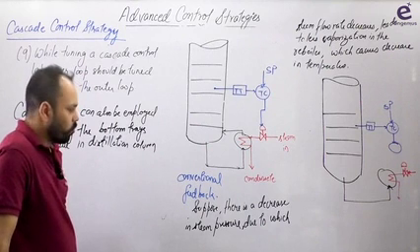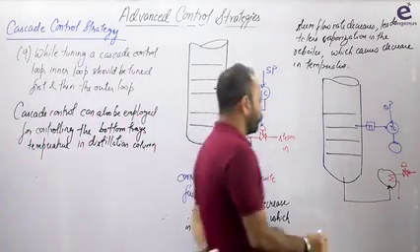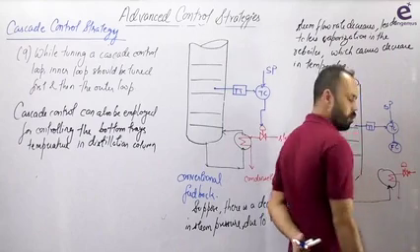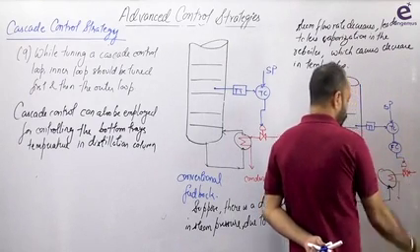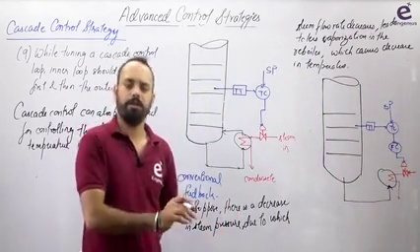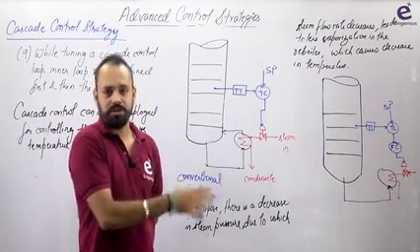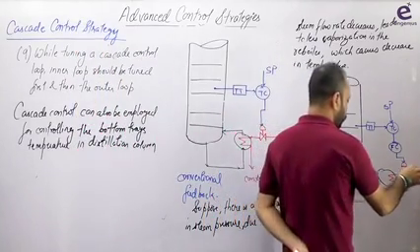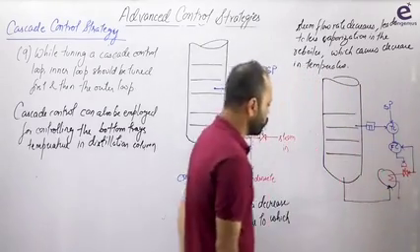Now this flow controller is going to measure the flow rate, right? So this flow controller FC is going to measure the flow rate of the steam, and then it will correct the steam change. Pressure को correct नहीं करेगा; pressure की वजह से flow rate बदला है, तो flow rate को correct करेगा, right? Increasing the pressure is not in its control, वो तो कहीं और से आ रहा है. So it should also take the measurement of the steam flow. So suppose the measurement is coming from here.